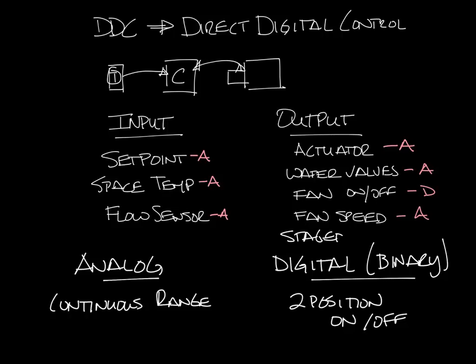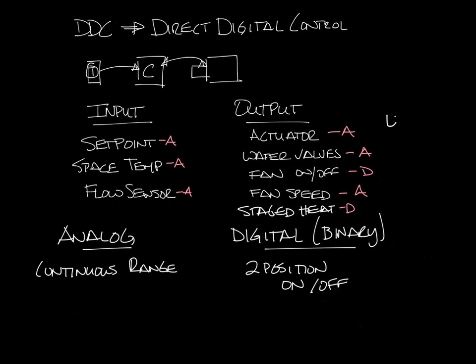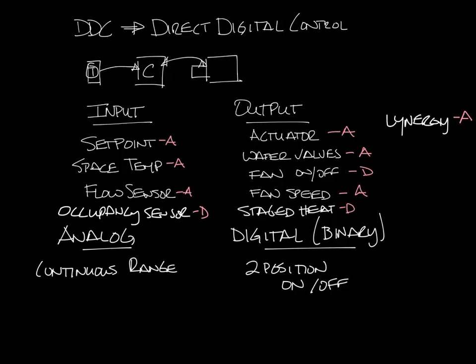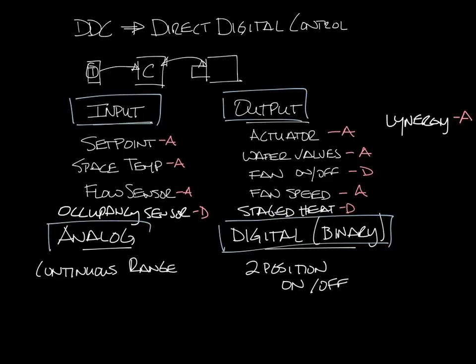Some more examples: stages of electric heat would be digital outputs — you would turn each stage on and off — but proportional heat like our Lynergy heater would be an analog output. On the input side, an occupancy sensor would be a digital input to the controller; it would indicate whether the space is occupied, yes or no. That's just a few of the inputs and outputs, both digital and analog, that you can have on a VAV box.